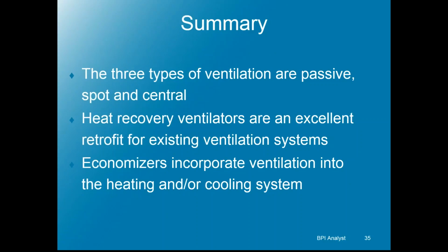All right, so in summary, and then we'll cover some problems before we take questions. There are 3 types of ventilation systems: passive or natural ventilation, spot ventilation, which is an acceptable method if the spot ventilation can also operate continuously. It's an acceptable method of ventilating a home under California code. And then the central ventilation system, so the balanced system or the HVAC integrated system, which I said is not typically recommended, but it's out there. And then heat recovery ventilators are great for minimizing the negative energy implications of ventilation systems. And then economizers are there, typically commercial though.